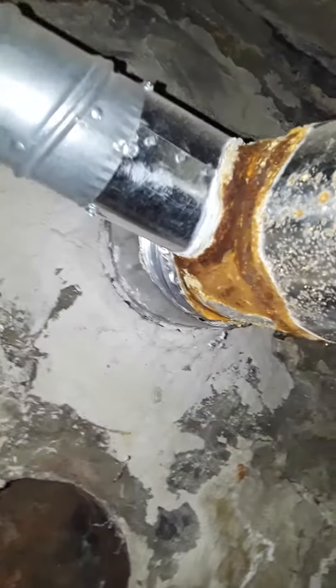I don't know if I'm getting any of that on video, but I suspect that liner is not a true liner. I'll review the video I just took, but we may have to go to the 90 percent furnace and vent out through this window opening right here. There's obviously something wrong with that liner.